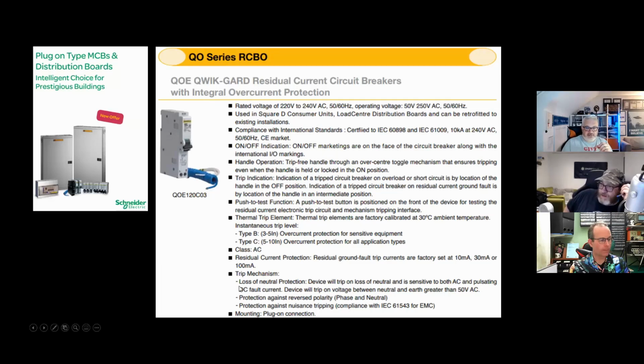So if I can get my mouse over this, this is an old Square D with a fly-lead neutral and functional earth. But at the bottom here, it says trip mechanism, loss of neutral protection. Device will trip on loss of neutral and is sensitive to both AC and pulsating DC. Device will trip on voltage between neutral and earth greater than 50 volts. So this technology, this measuring rise in voltage, has been around for donkeys.